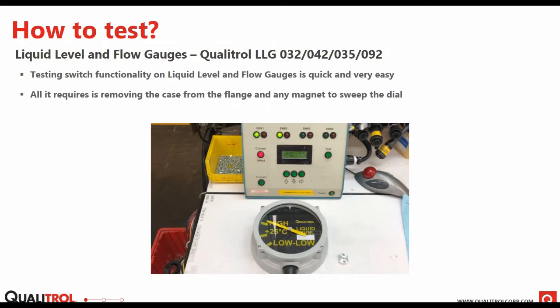So we'll start out here with our liquid level gauges, and flow gauges can also be tied into this group because they function on the same basic design. So the liquid level gauge is used for a few reasons on the transformer. It's obviously to detect a low oil level, which, if it gets low enough, can result in catastrophic failure. And it's also used for filling the transformer and things of that nature. Most of the time, the switch contacts are at the low setting on the liquid level gauge to indicate a low oil level.